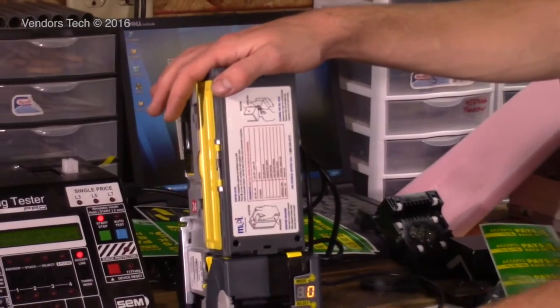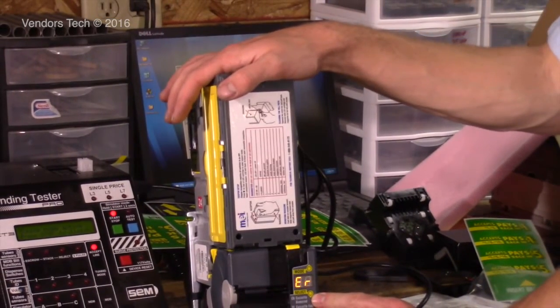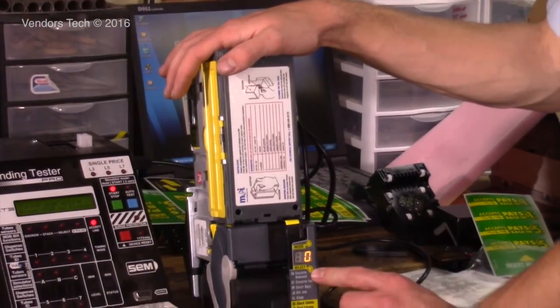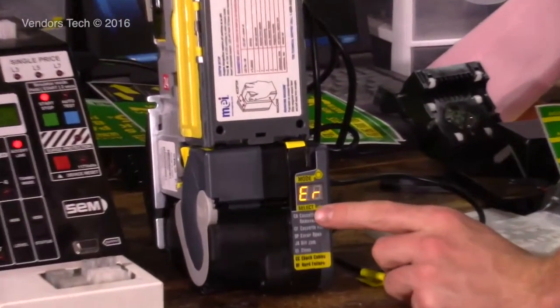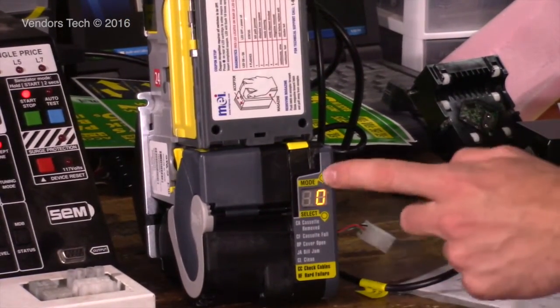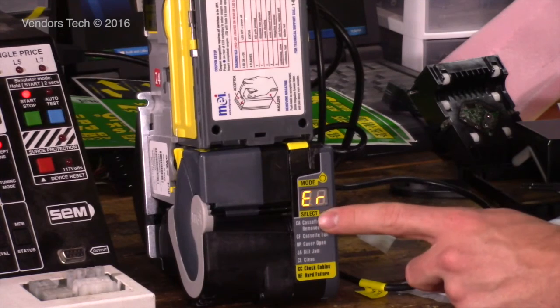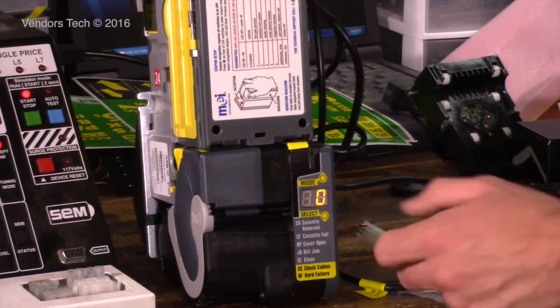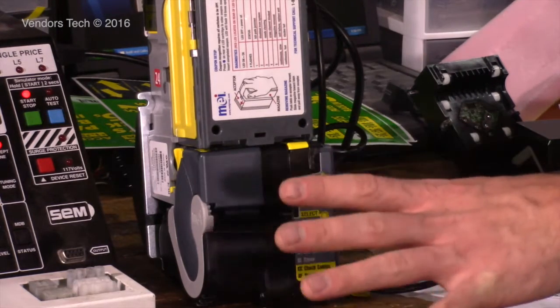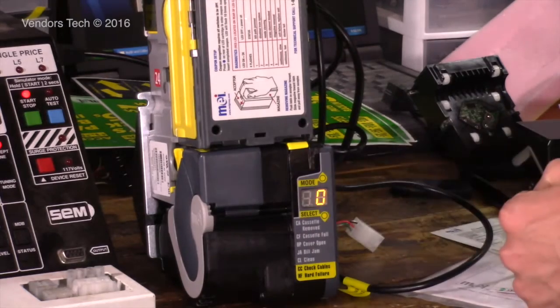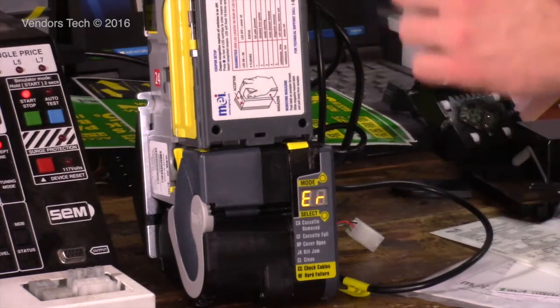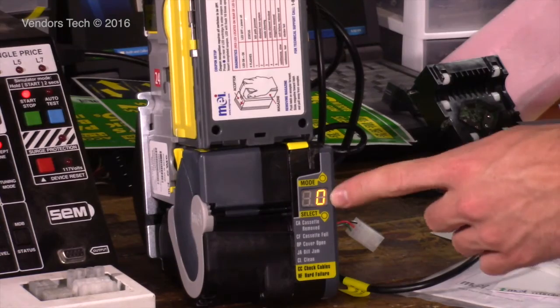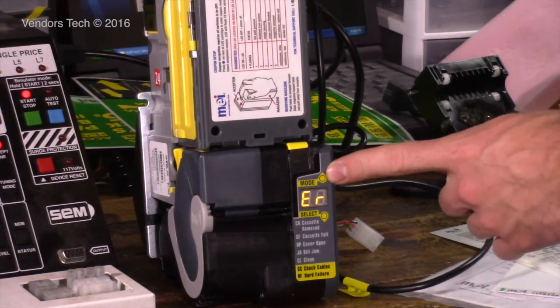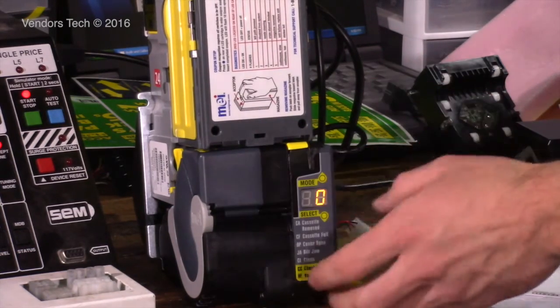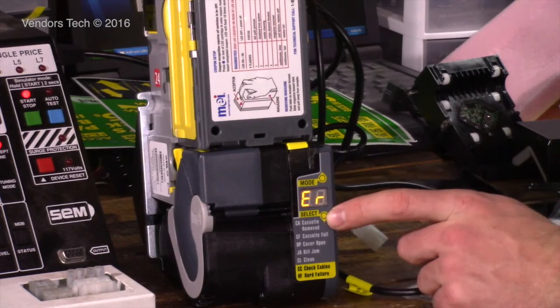But anyway, here's the process for getting in and calibrating this validator. You have two buttons here, a mode button and a select button. We're going to hold down the select button until the display briefly flashes 2 lines. Then, within the next 2 seconds after those 2 lines flash, you're going to go up to your mode button and hold that down until it gets into your service mode.